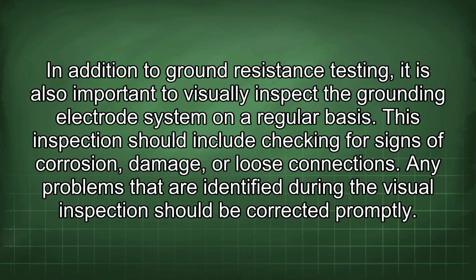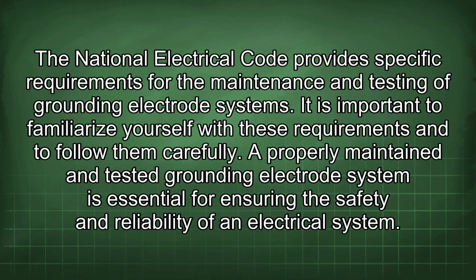In addition to ground resistance testing, it is also important to visually inspect the grounding electrode system on a regular basis. This inspection should include checking for signs of corrosion, damage, or loose connections. Any problems that are identified during the visual inspection should be corrected promptly. The National Electrical Code provides specific requirements for the maintenance and testing of grounding electrode systems. It is important to familiarize yourself with these requirements and to follow them carefully. A properly maintained and tested grounding electrode system is essential for ensuring the safety and reliability of an electrical system.